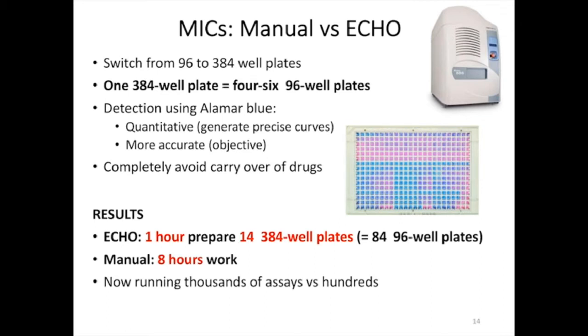With the Echo instrument, we are now able to prepare many more plates in a particular time. For example, with the Echo, in 1 hour we are able to prepare 14 384 well plates, which approximately correspond to 84 96 well plates, and the same number of plates that we prepare in 1 hour with the Echo will take us at least 8 hours to do manually.